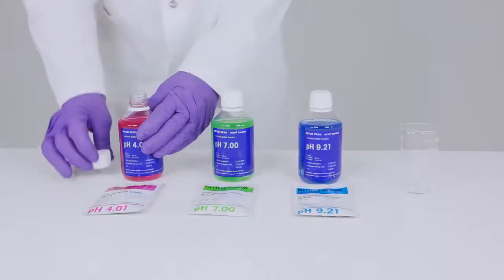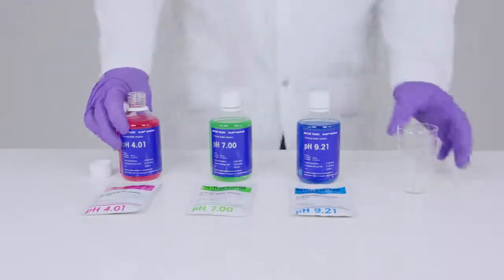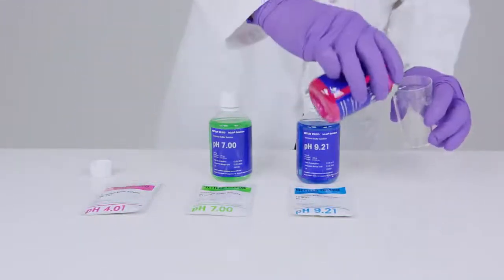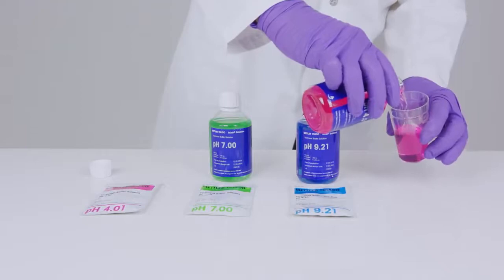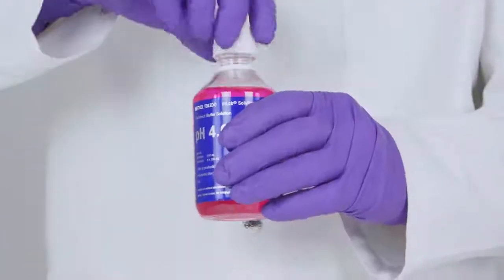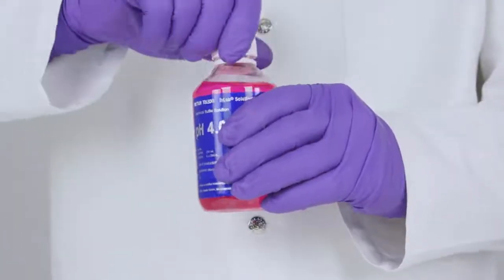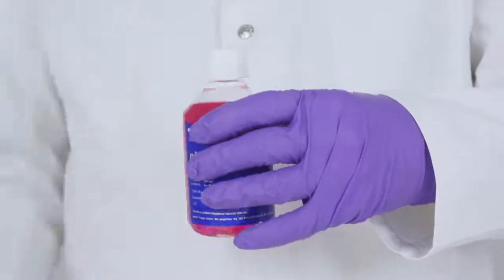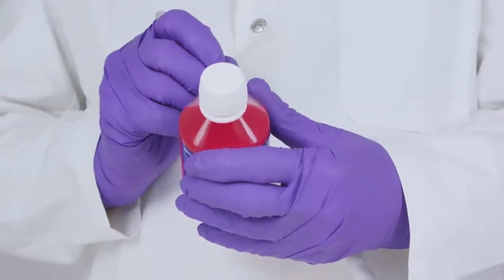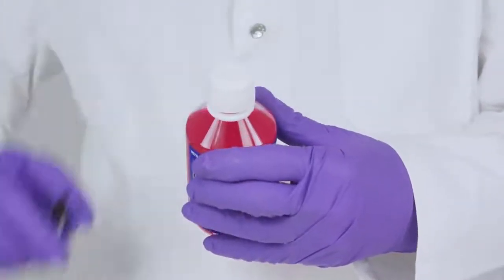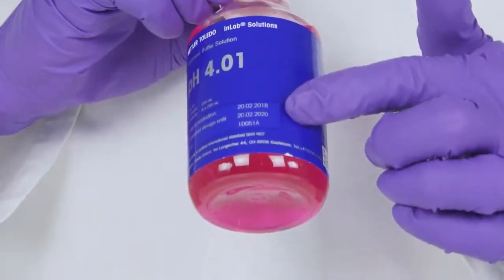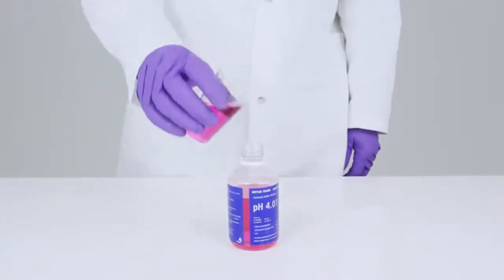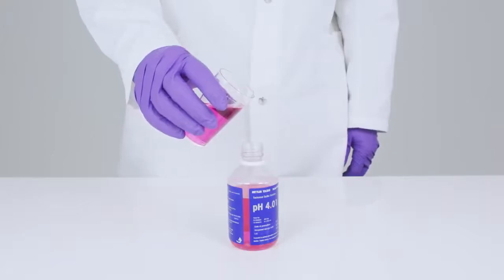It's almost time to dive in, but before we do, it's important to note that using fresh buffers is highly recommended. Sachets are guaranteed to be fresh. New bottles are too, but they must be closed immediately after use and marked with the date and time. Just like fine wine, although buffers don't get better with age, so check that expiry date. When you have poured a buffer for use, don't try and pour it back in, as it may introduce contaminants to the bottle. Okay, Hans, the big moment has arrived.